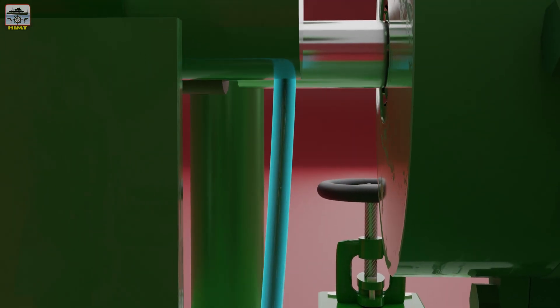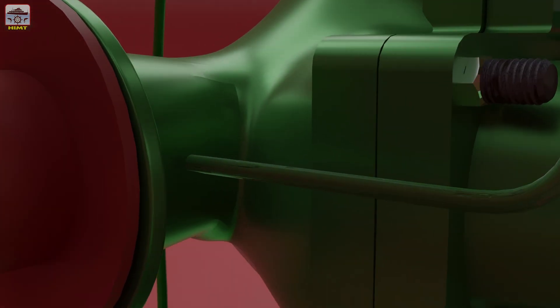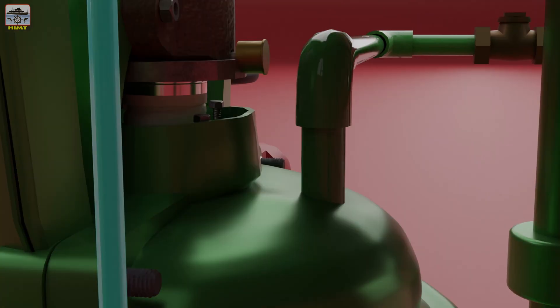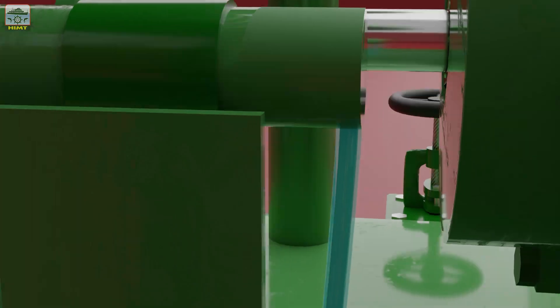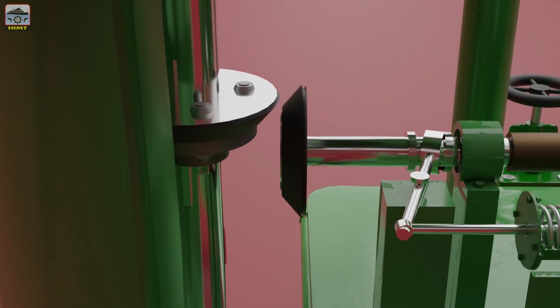This side of the cylinder is connected to the discharge side of the centrifugal pump by a pipeline. When the centrifugal pump builds up discharge pressure, the pressure will force the piston rod to protrude out against the spring force which will disengage the primer pump.